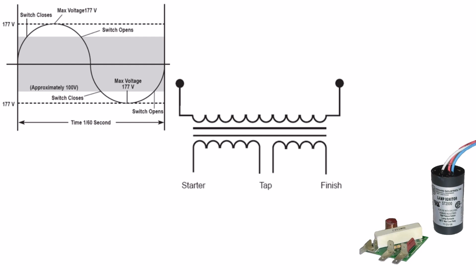Here's the deal. When you flip the switch on an HPS light, it doesn't just light up instantly like a regular bulb. It needs a huge jolt of electricity to get going, anywhere from 2500 to 4000 volts. But wait, the power coming out of your wall is only 120 or 240 volts. So how does it jump that high? Enter the starter. This little device boosts the voltage just long enough to get the lamp started, like a car starter. Once the lamp is running, the starter shuts off and stays off until the lamp is turned off and restarted.